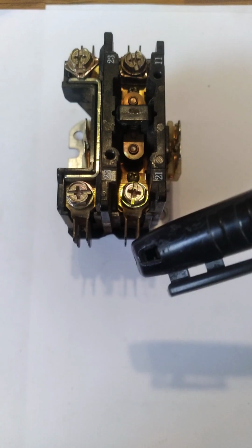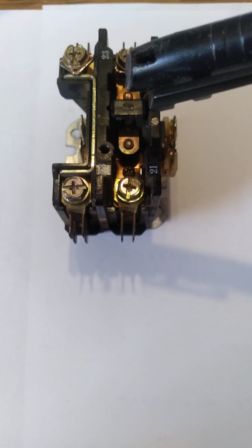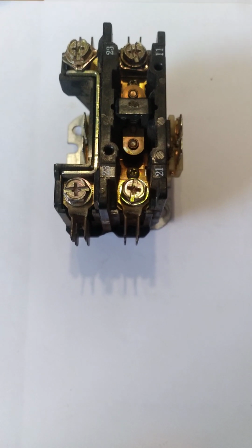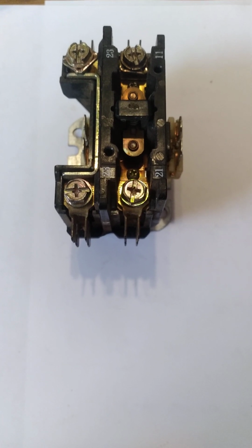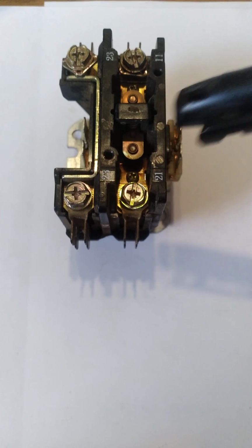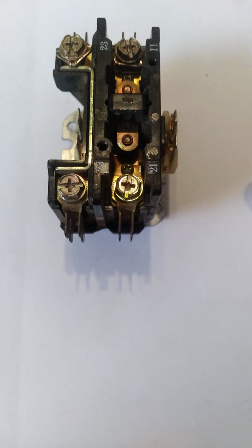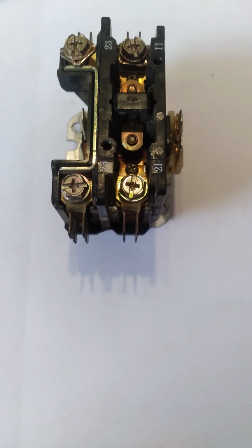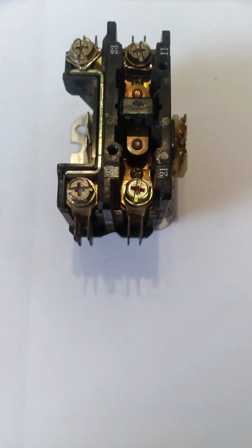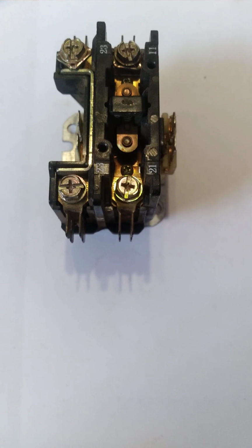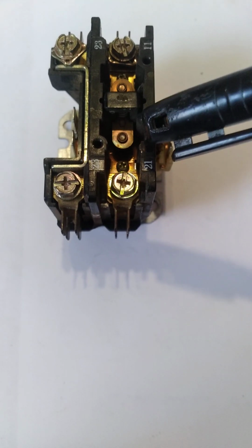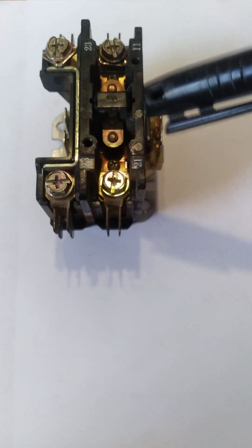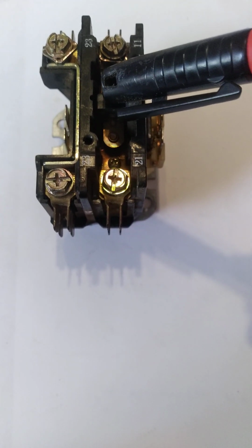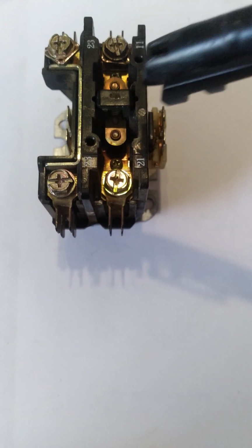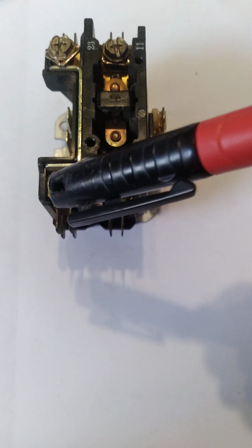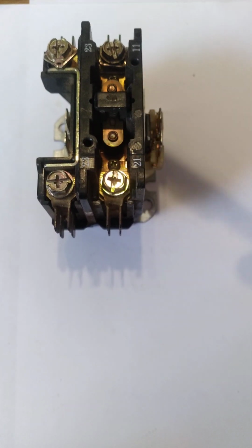So why wouldn't we just wire this straight in and bypass this? There are times where one needs the voltage, but they need the voltage to cut on and off. So one could think of this as a switch, which works electrically. Say, for instance, your light switch at your house, that would be you flipping it on manually. This would work electrically. So once the thermostat calls for cool and the low voltage wire from your thermostat sends a signal here and here, this closes, as you can see. Boom, boom. Once closed, we make a contact. 240 here, 240 here goes to 240 here.